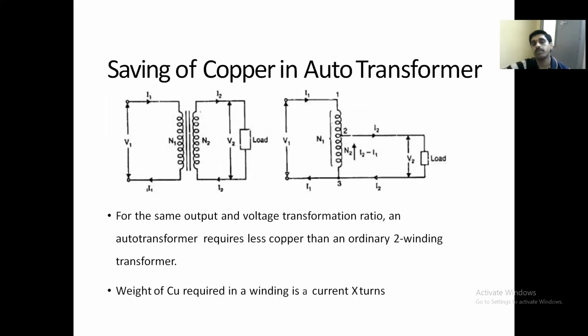So what is the saving of power? Saving of copper in the auto transformer. For the same output and the same voltage transformation ratio, the auto transformer requires less copper than an ordinary two-winding transformer. Compared to a normal two-winding transformer, it requires less copper. So how? Let us see.